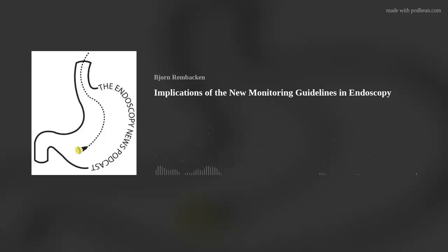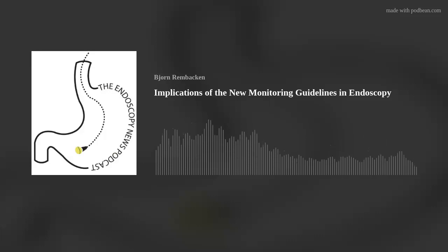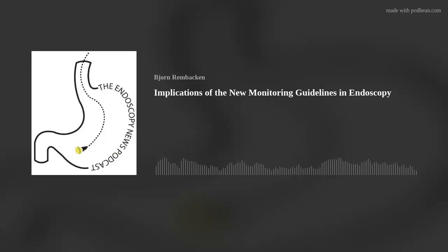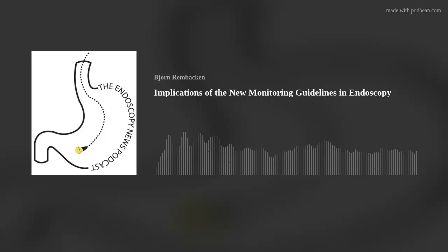You get a waveform. It's a closed circuit on an anesthetic trolley, isn't it? So is there anything you can deduce from the waveform, from changing the waveforms? Yeah, absolutely. As long as the sampling port is somewhere near where the carbon dioxide is being produced, it will produce a waveform that you can interpret together with other clinical signs, which will give you a very good idea about the adequacy of the patient's breathing. In anesthesia, we typically use it with relatively closed systems such as an endotracheal tube or a laryngeal mask airway, and then the peak value of the carbon dioxide equates to the value in the blood.